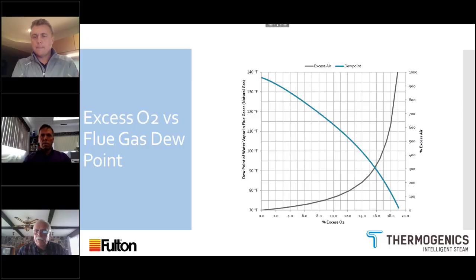Paul, it's JJ. We have a question on the chat line here. Approximately how great are the efficiency savings from reducing the pressure across the steam system, especially where PRVs are in many of the endpoint units? That's a great question. I'm actually really thrilled it came up because that is circumstantial. It's going to depend on your system, but there is one very important maintenance related issue that has come up almost at every application I've seen.